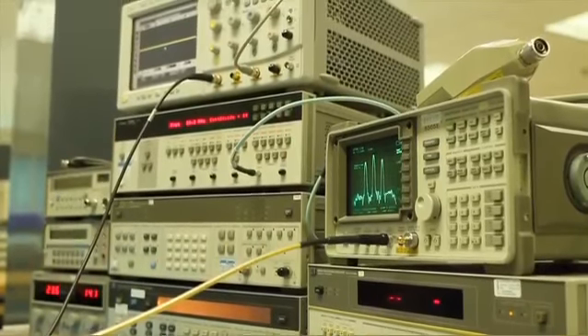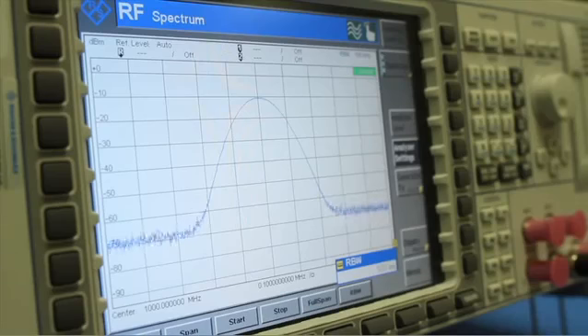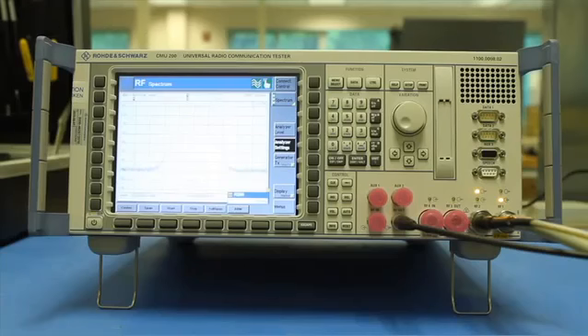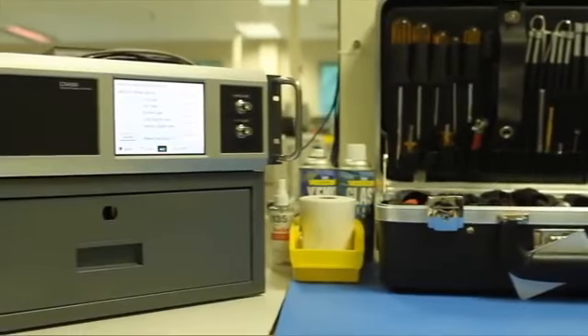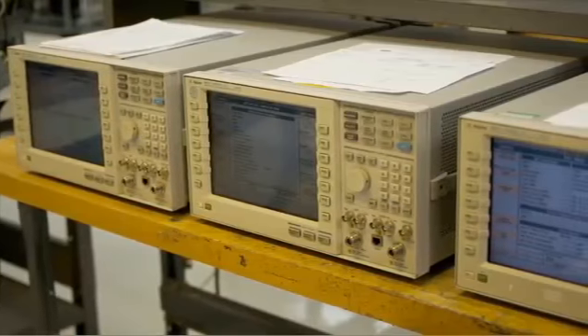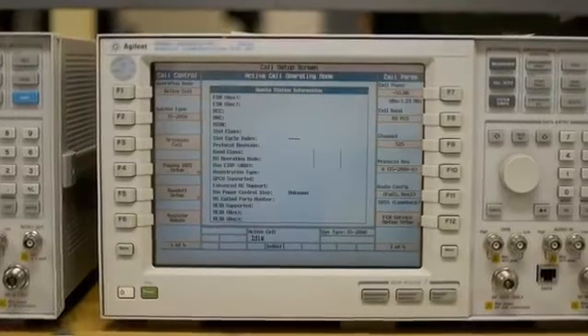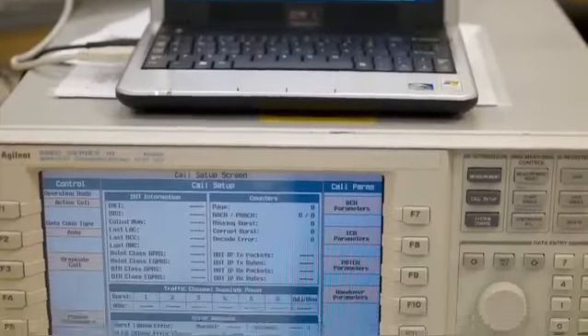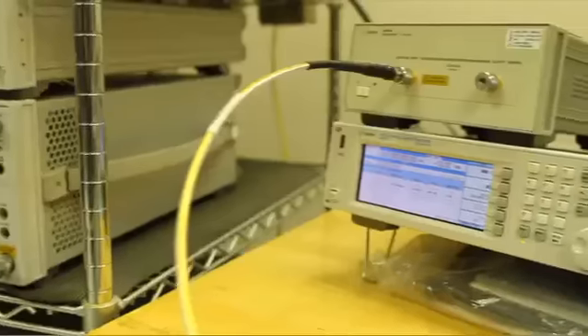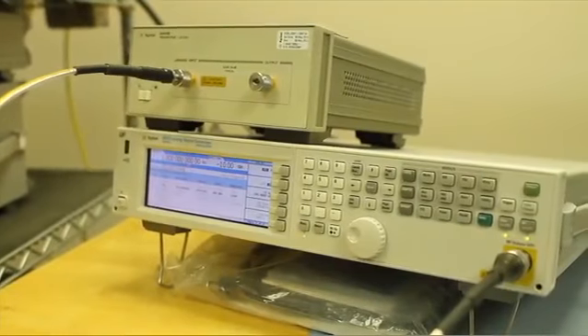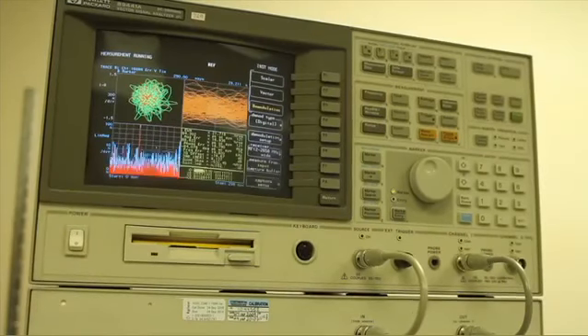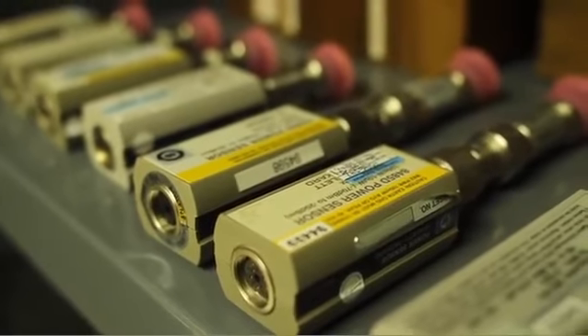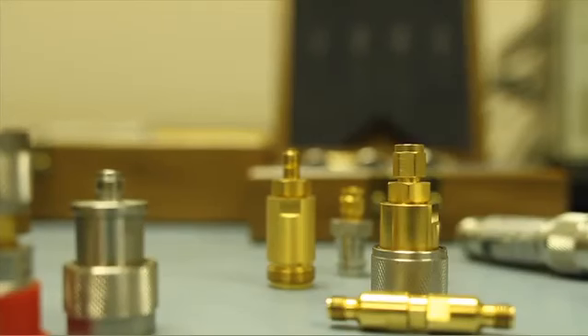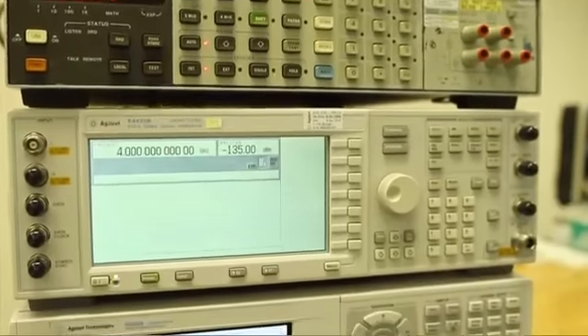Another one of our mid-frequency test benches has very versatile capabilities for scopes and medium-range spectrum analyzers, maybe up to 26.5 gigahertz. We also have capability for calibration on a lot of mobile phone test systems. In order to cal a piece of test gear properly, you need the proper standards with the proper accuracy. The general rule of thumb is a 4-to-1 ratio or better, meaning that your standard must be 4 times as accurate as the piece that you're calibrating.